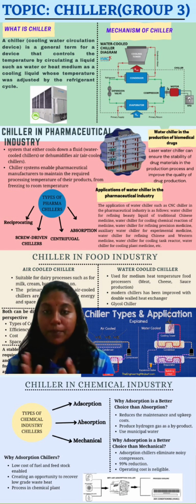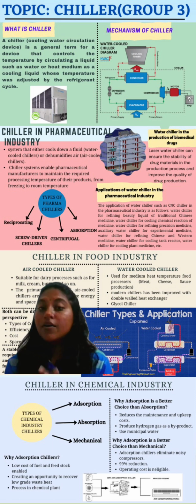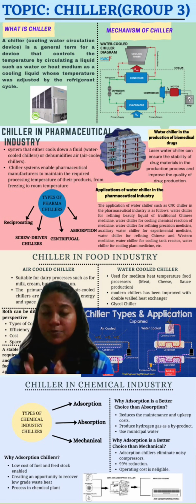Third, centrifugal chillers are very common, with more than 80,000 operating in North America. Their evaporator functions as a heat exchanger to remove heat from chilled water. Fourth, absorption. A heat source provides absorption chillers with the energy to cool water. These chillers use water as the refrigerant and lithium bromide as the absorbent.